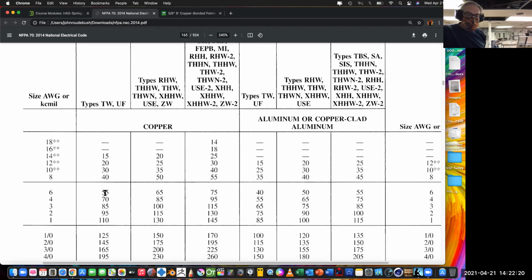We're not going to be able to bring more than 60 amps into this system that we're building because the breaker will trip. So our charge controllers and all of our equipment are protected by that overcurrent protection device, that circuit breaker. We also know that even though our wire is going to be on for more than 3 hours at a time, we still have this margin of 75 in there. I can tell you this wire works just fine. It has been here for almost 10 years running on 6-gauge wire, and it's not a problem. It doesn't get hot. It's plenty big. A lot of times we fail to realize that our solar systems aren't running at 60 amps full blast all the time for more than 3 hours.